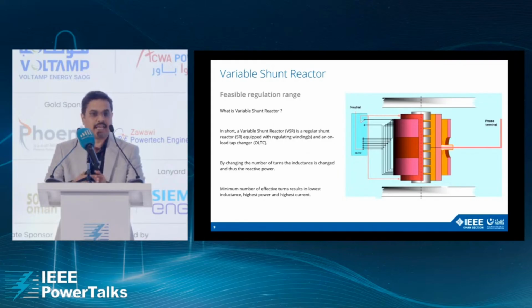Whenever you have a demand for higher inductance, it can add turns without creating much transients in the system. So it's creating a variable inductance, and when this inductance reacts with the frequency of the transmission line, you get variable reactance. So without creating much turbulence or transients in the system, a variable shunt reactor, with the help of an on-load tap changer, can create or absorb time-variable reactive power from the system.